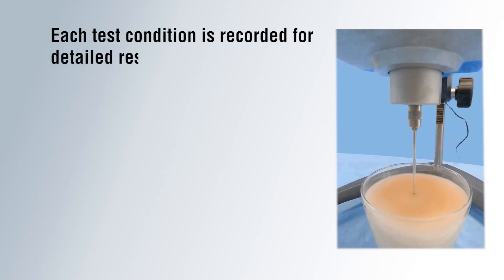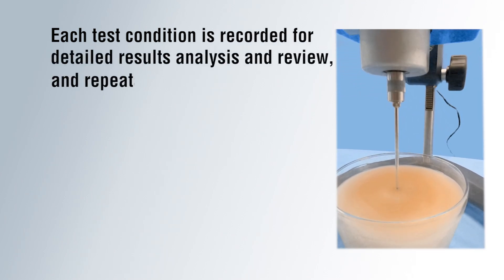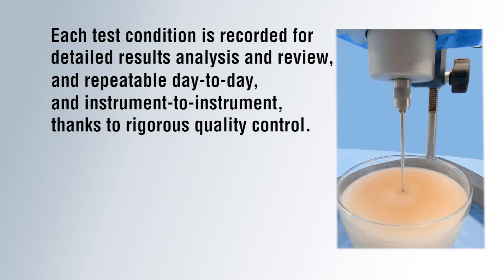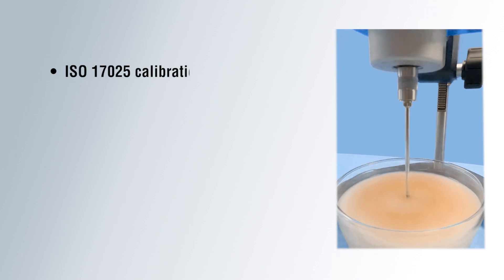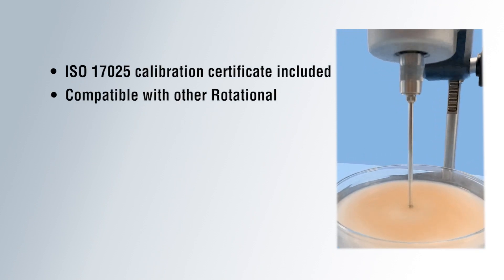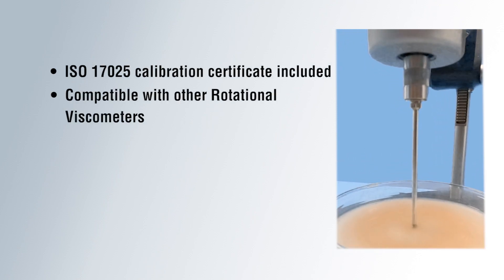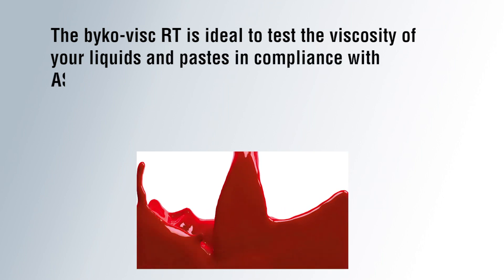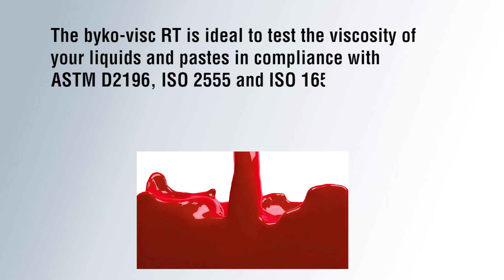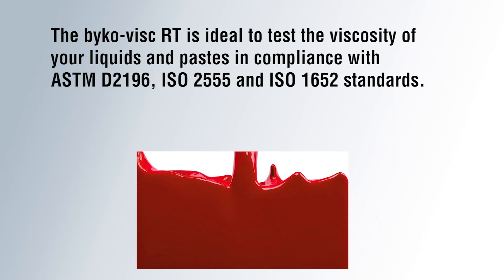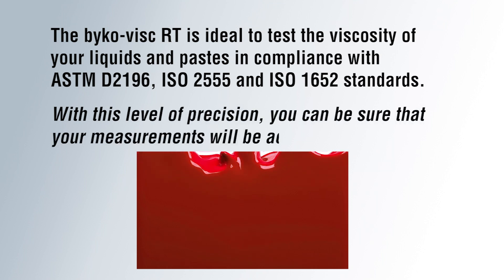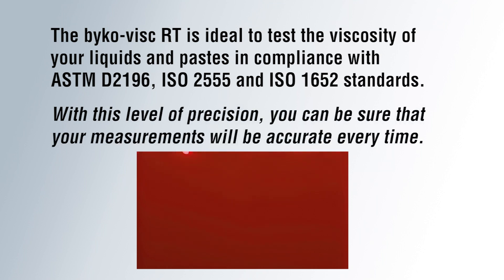Each test condition is recorded for detailed results analysis and review, repeatable day-to-day and instrument-to-instrument thanks to rigorous quality control. An ISO 17025 calibration certificate is supplied with each instrument to confirm this performance. The byko-visc RT is ideal to test the viscosity of your liquids and pastes in compliance with ASTM D2196, ISO 2555, and ISO 1652 standards. With this level of precision, you can be sure that your measurements will be accurate every time.